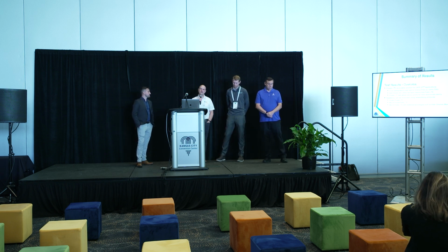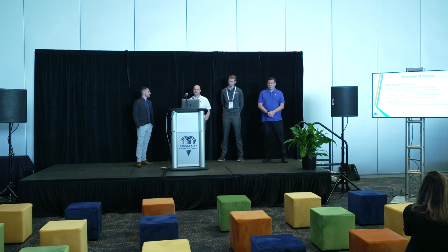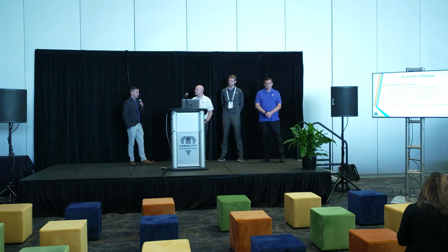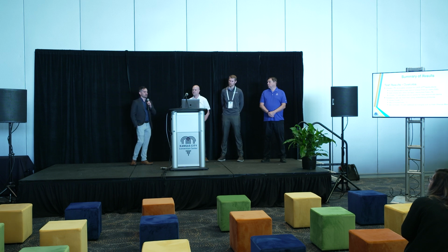Usually utilities are trying to prevent that island from forming within 2 seconds total, but that includes breaker operation time, communication time, and any controls involved. So that's a total time. Generally speaking, from a communication point of view, 100 milliseconds for this type of application would certainly be acceptable. Yeah, that's really good information, because you don't want the comms piece being 1.9 seconds of that 2 seconds, because you're going to end up with damage or potential harm to people.